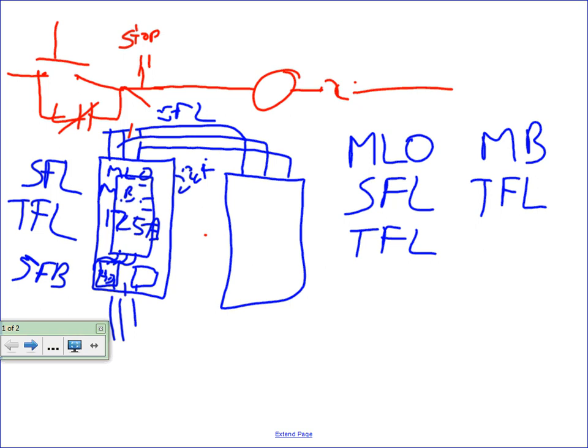And someday, I mean, I don't know how we would do it, but Cedar Rapids, Iowa is where our test lab is. It's kind of fun to go down there sometimes and watch them blow stuff up. I mean, they can generate up to, I think, 300,000 amp fault current in that facility. It's not as much fun to watch a panel board, but some of these bigger products, we have to test our switchboards and our switchgear. You can actually start seeing the phase buses moving because of the fault stresses within it under a fault condition.